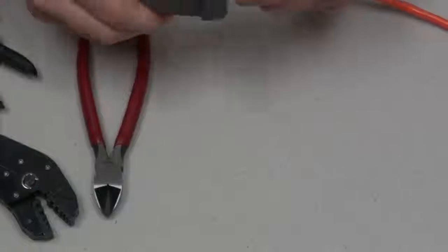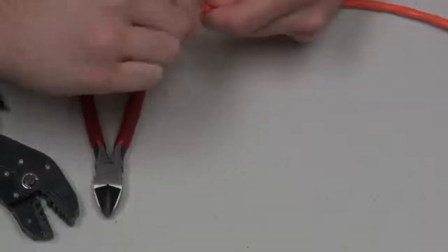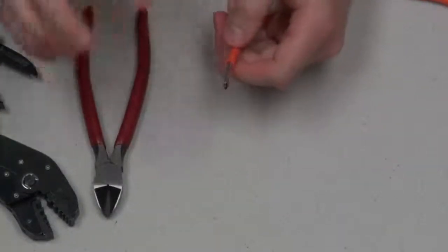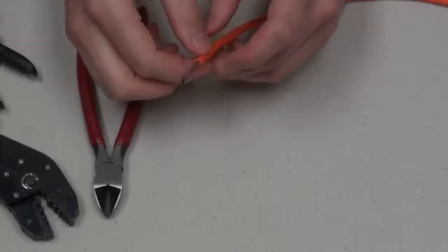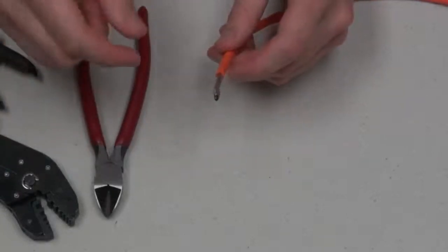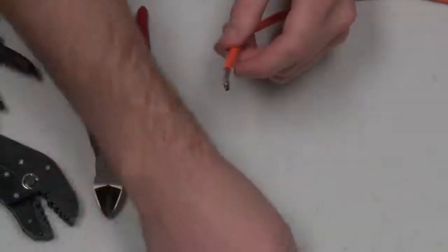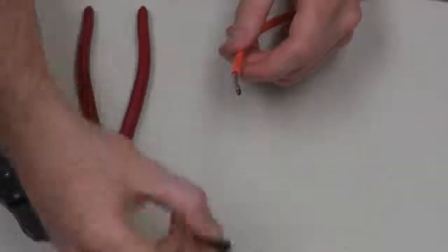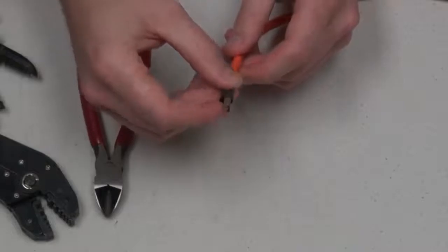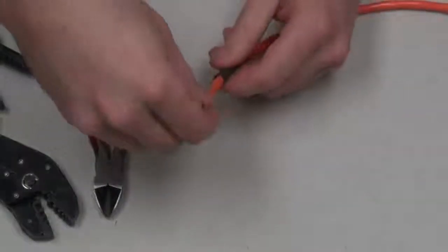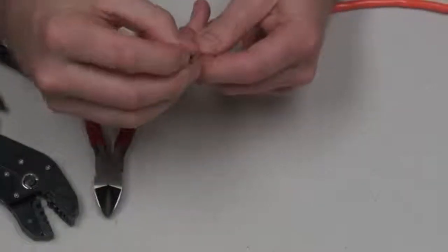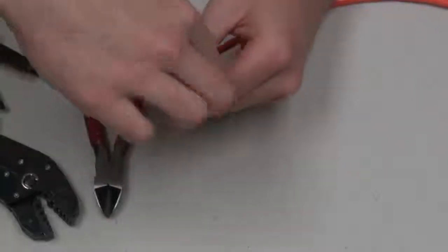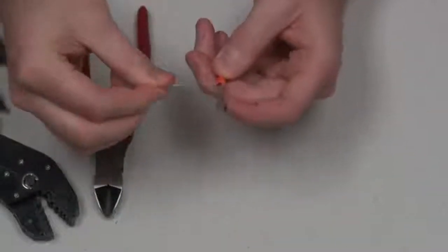Go ahead and strip the outer jacket. Separating, but also being sure not to damage the interior. At this point, it's a little bit different for me. Depending on the size heat shrink you're using, it can get tough slipping it over the wire and the ferrule when you're using three wires that are all ferruled. So I like to go ahead and just slip the heat shrink over now. But anyway, again, we will separate the shield wire here that is on the outside. And since we're keeping it intact this time, we just want to kind of separate it over here and leave it off to the side for the moment.